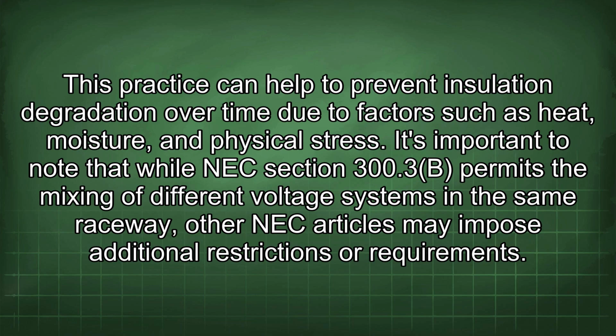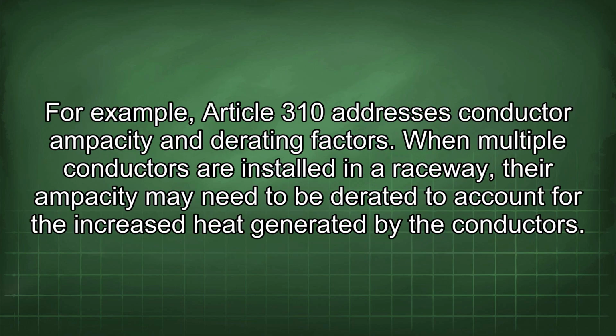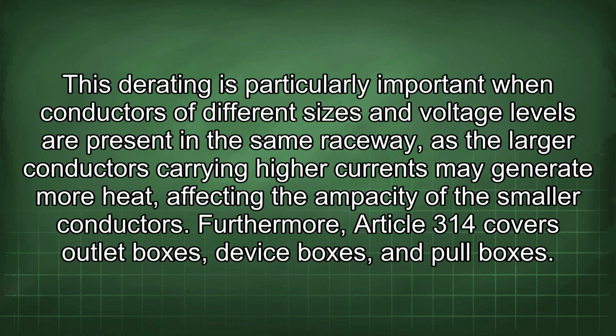It's important to note that while NEC Section 300.3(B) permits the mixing of different voltage systems in the same raceway, other NEC articles may impose additional restrictions or requirements. For example, Article 310 addresses conductor ampacity and derating factors. When multiple conductors are installed in a raceway, their ampacity may need to be derated to account for the increased heat generated by the conductors. This derating is particularly important when conductors of different sizes and voltage levels are present in the same raceway, as the larger conductors carrying higher currents may generate more heat, affecting the ampacity of the smaller conductors.